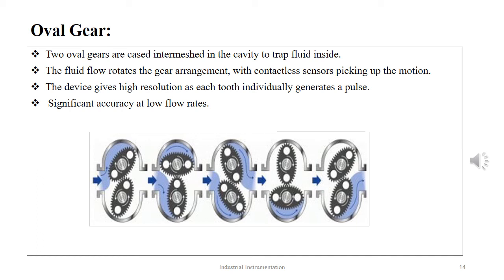Newer designs of this type of meter use servo motors to drive the gear. This eliminates the pressure drop across the meter and also the force required to drive the gear is normalized. This eliminates the force which causes the slip flow. This mainly applies to smaller sized meters and significantly increases the accuracy at low flow rates.